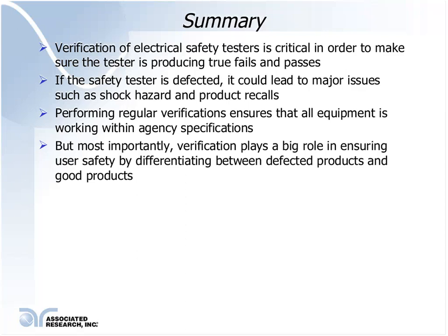And additionally, we know that microprocessor controlled safety testing devices also allow for programming and saving verification procedures. Such procedures can be set up to include working instructions and data acquisition as well.